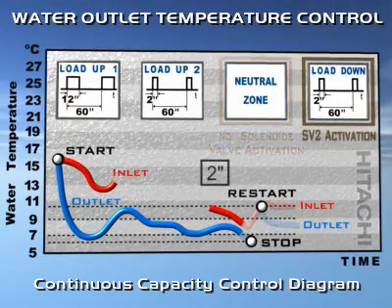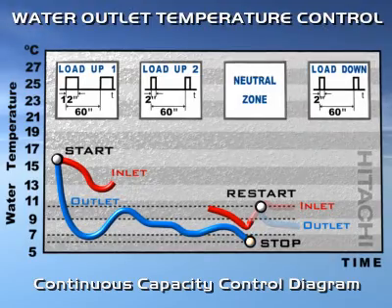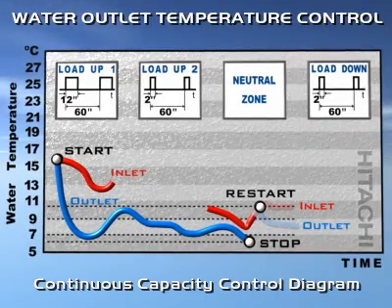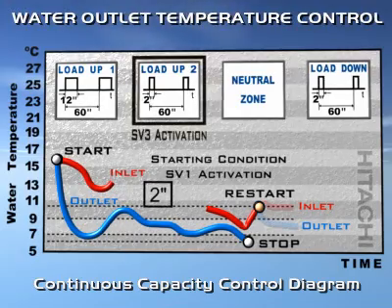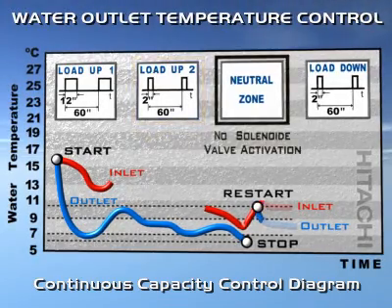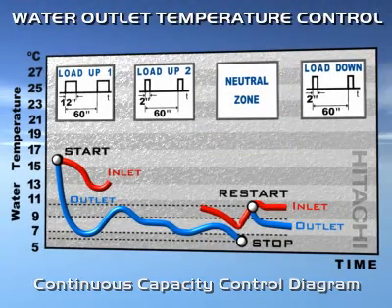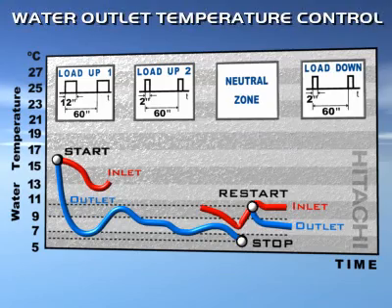The signal has a variable length, therefore the slider repositioning will be variable according to the control band. When in the band Load Up One, the signal will last for twelve seconds. When in band Load Up Two or Load Down, the signal will last two seconds. When in the Neutral band, the slider will stay where it is, as will the capacity.